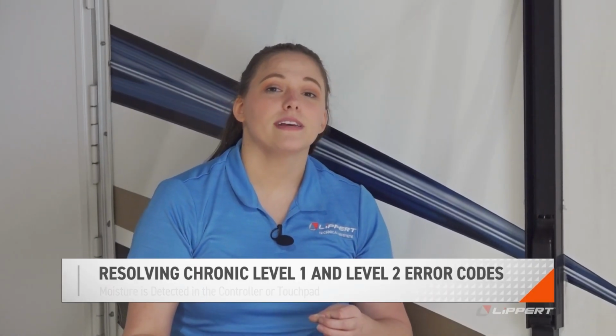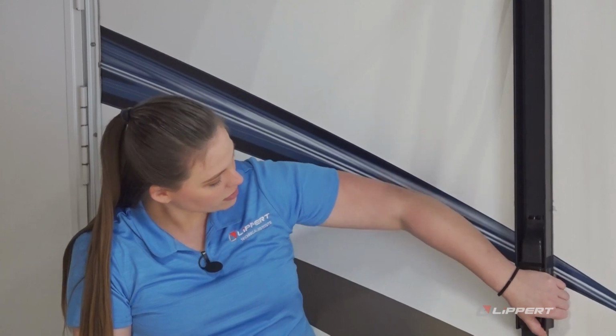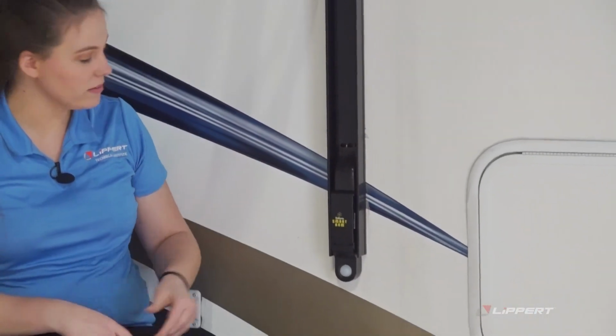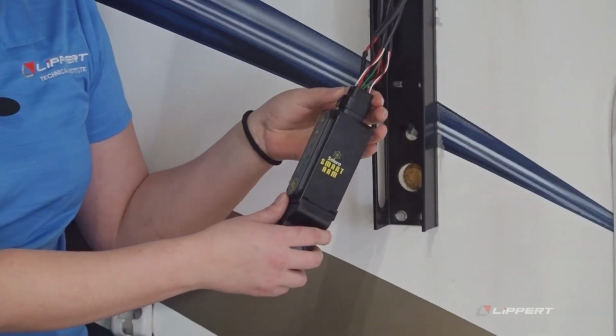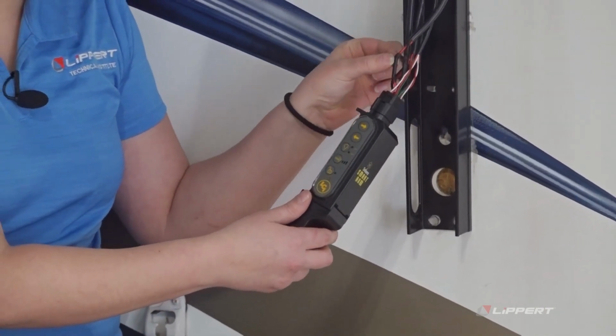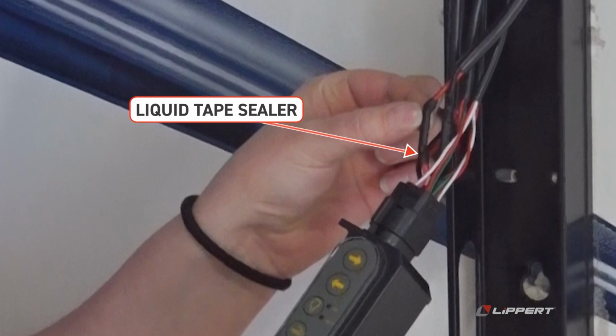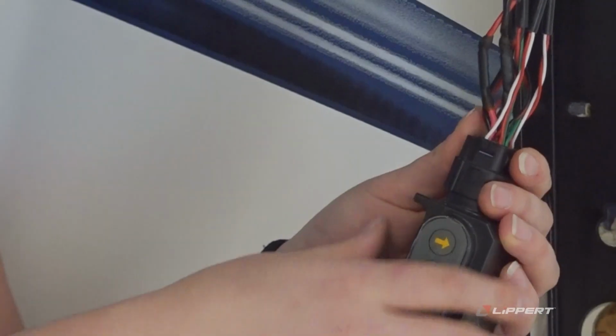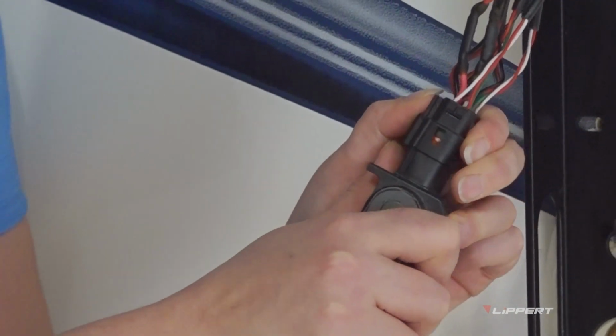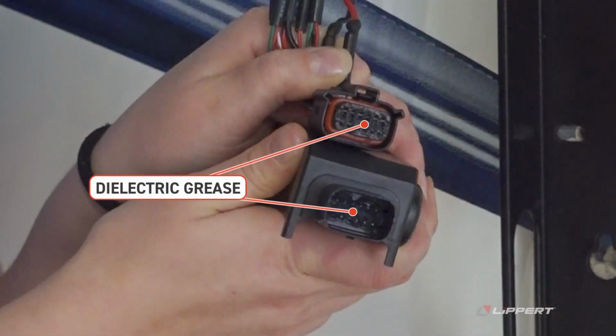If your system continually senses a fault code 1 or fault code 2, you may need to perform a moisture mitigation procedure. You can find that documentation on our support site if you feel confident performing this, or you can contact a service center and they can perform it for you. If you're inspecting your touchpad to see if this procedure has been done, remove your touchpad and harness, and then you can check to see if any liquid tape sealer has been applied to your harness connections. While everything's disassembled, you can check for dielectric grease at your connection, and there should also be some in your control board.